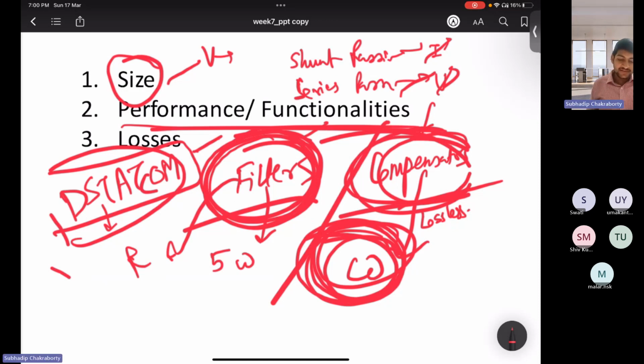And obviously these filters also can eliminate multiple harmonic contents, but eliminating multiple harmonic components using the filters, the number of components will increase. So we prefer the DStatComs or the UPQCs in such cases where there are multiple harmonic problems. But in order to eliminate some very higher order frequencies, we can use RC filters based first order passive filters, right? To eliminate such switching ripples. So these compensators are always accompanied with filters, and they both work together to achieve the best possible out of a system.